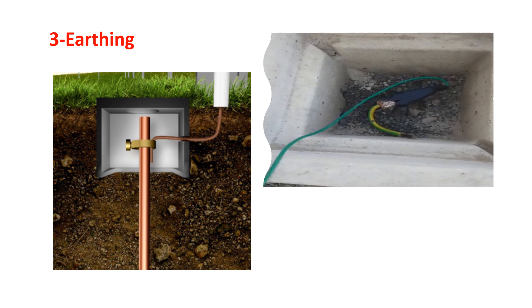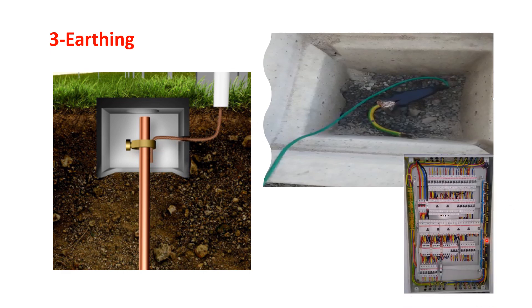The third and most important task is earthing. Earthing means a solid copper rod that is inserted into the ground. From the copper rod, one wire is connected to our distribution board. All the earth wirings from equipment are connected to this system. So the earth wirings from each appliance are connected to the equipment body, and then back to the earthing rod via the distribution board.